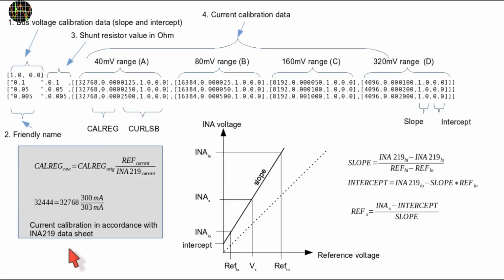If you look at the gray box, this is what the INA219 datasheet recommends for calibration. Basically, you tweak the calreg value, which a chip needs to convert the shunt voltage into a current. You do that by picking a pair of reference and corresponding INA219 readings to calculate a scale factor, which you then apply to the original calreg value to get the new calreg value.